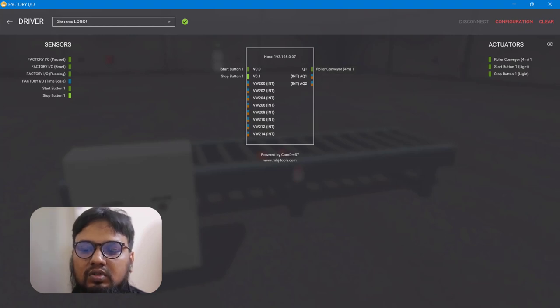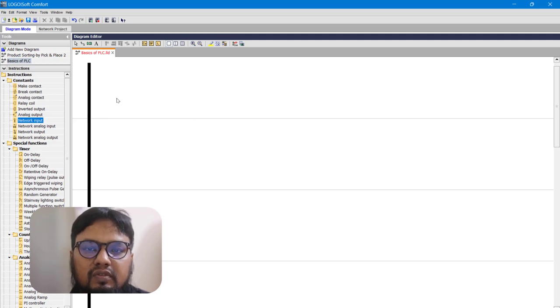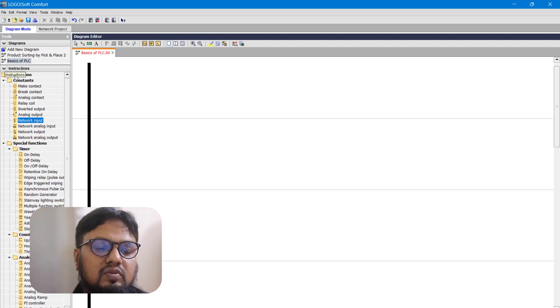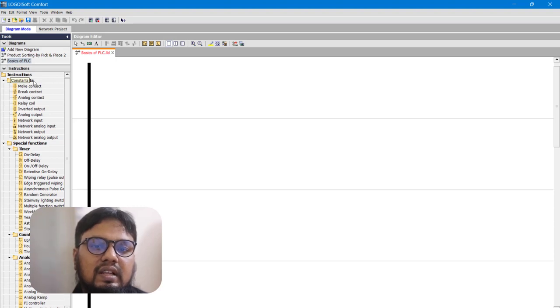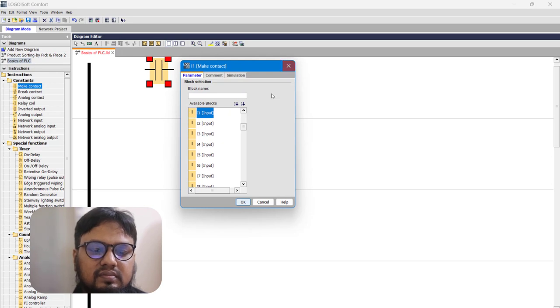Now we go to Logo Soft Comfort software, which we use for LOGO PLC programming — it's from Siemens. Open a new ladder file and rename it as your desired project. We have two inputs; to use them, go to Instructions, then under Constants we have digital and analog input/output contacts. A make contact is used for the start switch — let's bring it here and I'll assign I1 for now.